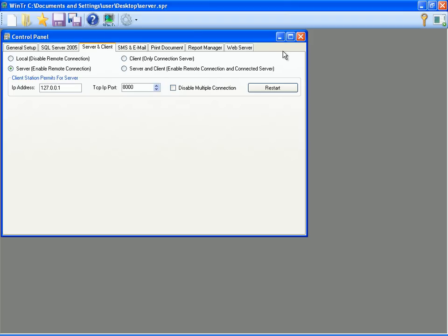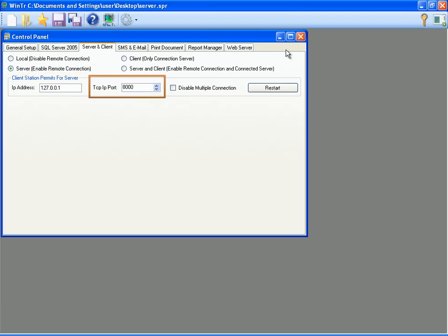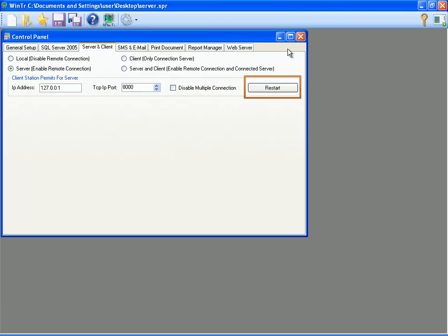If we want to set the project as allowing only one client from specific address, then we should enter the address in IP address field. TCP IP port is the port number for accepting remote connections. By checking disable multiple connection checkbox, we can determine if server accepts single or multiple client connection. We must click restart button for applying modifications. I am enabling the project for accepting multiple connections. After closing the control panel, I am saving the project.